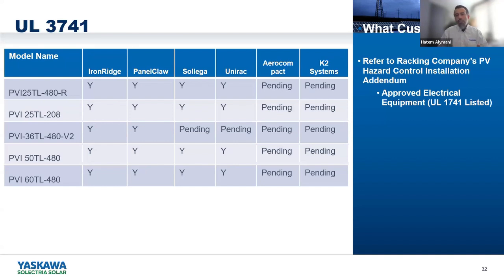to have to use rapid shutdown devices if you meet the other requirement that we discussed earlier. So this is, for example, our product line, and these are some of the most famous racking solutions out there. You can see, for example, with Iron Ridge, we are listed with all of our racking. Panel Claw, same thing. And when it comes to Unirac and some other manufacturers, we are either partially listed, or we are still in the process. It's better to say that the racking manufacturer is still in the process of testing the racking with our inverters and getting them approved. So yes, there's a very good chance here that you will be able to save, to reduce the cost on the project.